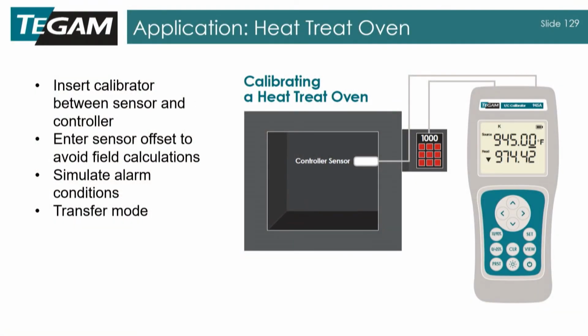Then there's another thing that can be done. You can insert your calibrator between the sensor and the controller. And if you know the offset of the sensor, you can put that into the controller or into the calibrator itself. So in AMS 2750, when you're doing this type of calibration, you actually have to manually calculate what the offset of the sensor is to come up with the correction factor for the controller or the monitor itself, because you've got to isolate the inaccuracy of the sensor from the inaccuracy of the controller.